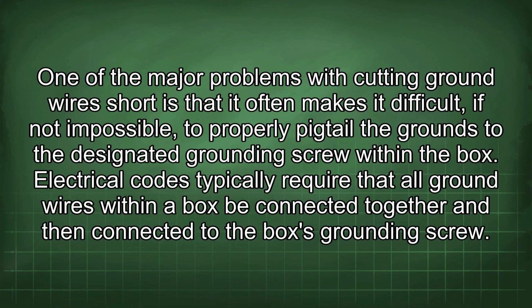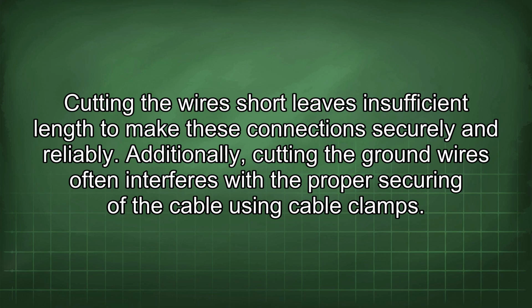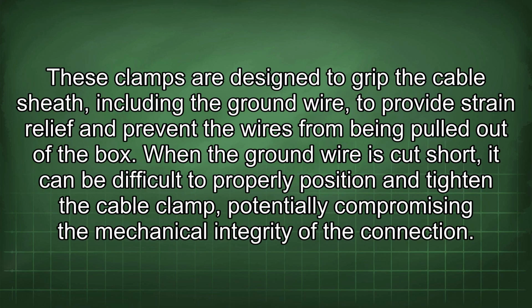One of the major problems with cutting ground wires short is that it often makes it difficult, if not impossible, to properly pigtail the grounds to the designated grounding screw within a box. Electrical codes typically require that all ground wires within a box be connected together and then connected to the box's grounding screw. Cutting the wires short leaves insufficient length to make these connections securely and reliably. Additionally, cutting the ground wires often interferes with the proper securing of the cable using cable clamps. These clamps are designed to grip the cable sheath, including the ground wire, to provide strain relief and prevent the wires from being pulled out of the box. When the ground wire is cut short, it can be difficult to properly position and tighten the cable clamp, potentially compromising the mechanical integrity of the connection.